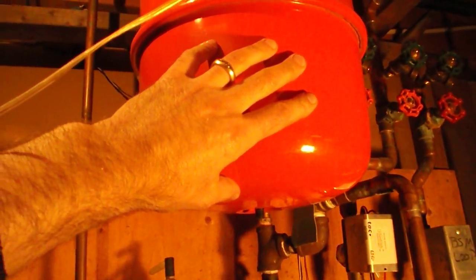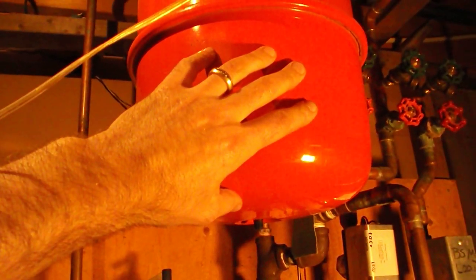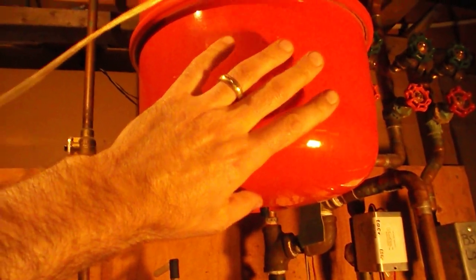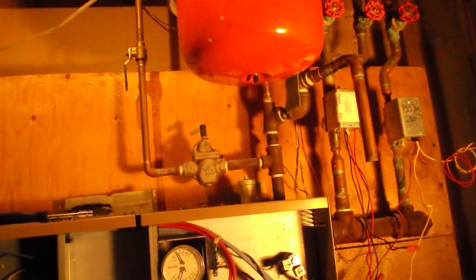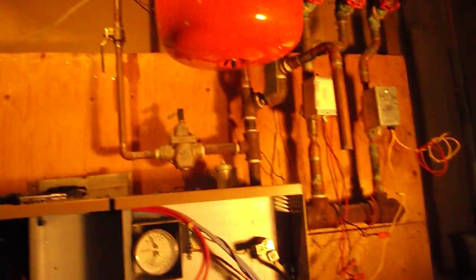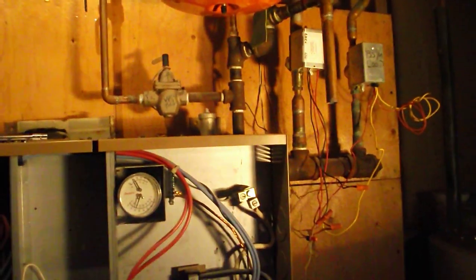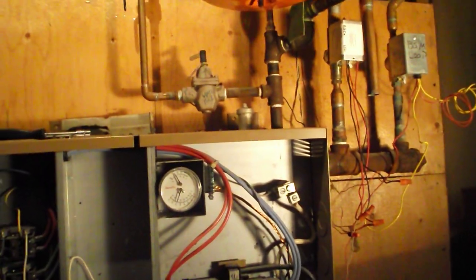And as the zone cools and the water contracts, the air pressure in here that was compressed now drives the water back up and into the zone. So it's a way of regulating the water pressure in there without constantly having to add and bleed off water. And that's something that we may want to look into as well.